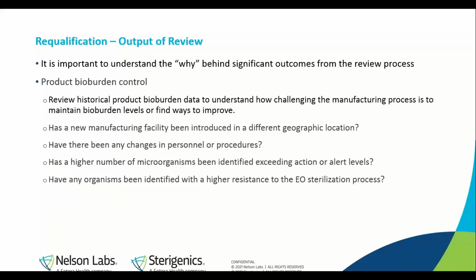Next, we'll go over the product bioburden control. This should be evaluated on a quarterly basis at minimum. You would want to review the historical product bioburden data to understand how challenging the manufacturing process is to maintain that level or find ways to improve that data. Has a new manufacturing facility been opened in a different geographic location? That would have an impact on the product bioburden. Have there been any major changes in personnel or procedures since the last requalification? Has a higher number of microorganisms been identified exceeding the action or alert levels as they've been established? Have any of the organisms been identified with a higher resistance to the EO sterilization process?